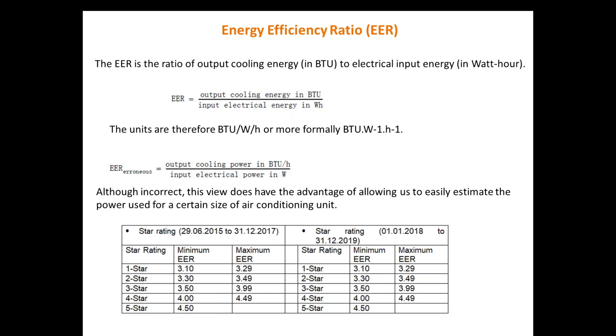Based on this energy efficiency ratio, various star ratings are given when you go to the market to purchase a refrigerator or air conditioner: 1 star, 2 star, 3 star, up to 5 star. Each refrigerator's categorization is based on its EER. For example, a 1 star refrigerator has minimum EER of 3.1 and maximum 3.29, for 2 star it's 3.3 to 3.49, and for 5 star it is 4.5. So higher output with less energy gets the 5 star rating, which is why EER is very significant in the industry for performance analysis of refrigeration systems.